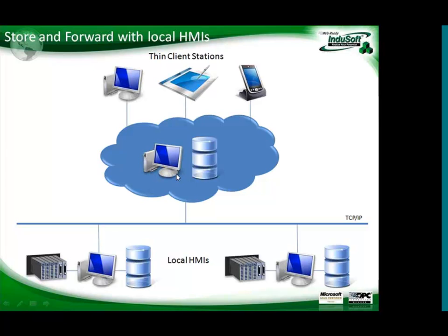So number one, you don't have to pull data from the RTUs. Each RTU can push data to the cloud, which makes the system even more scalable from the performance point of view. Moreover, if you lose the connection between one site and the cloud, the local HMI running the InduSoft Web Studio has the capability to store the information in a local database and eventually forward this information to the cloud. So you do not lose data even if you lose the connection with the cloud.